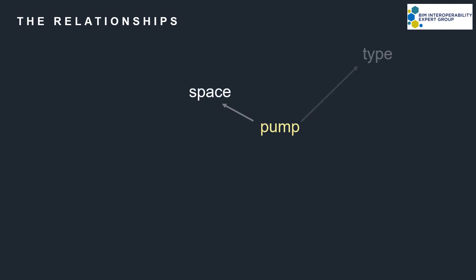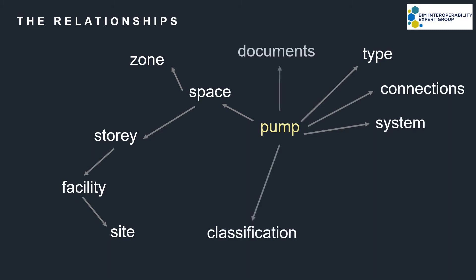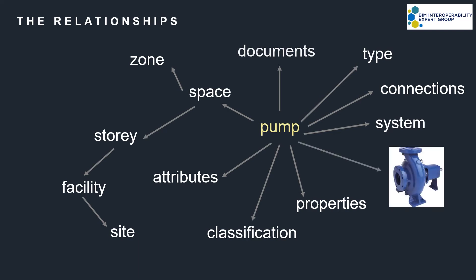It's the relationships which make IFC so powerful. An instance of a pump is associated with a space and a pump type. The space is located on a building storey and may be part of a zone. The storey is part of a facility, which sits on a site. The pump will also be part of a system, connected to pipe fittings, have detailed classification assigned to it, be referenced in documents, and have basic information like a name, description, ID, and properties like pressure. It might also have risk associated with it. And that's just one pump.